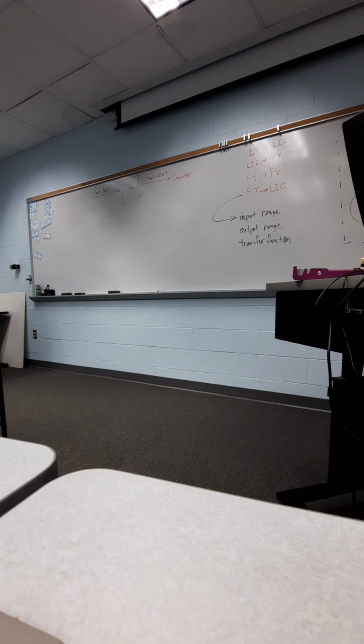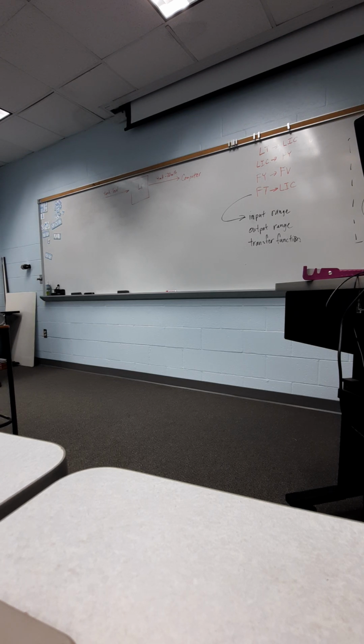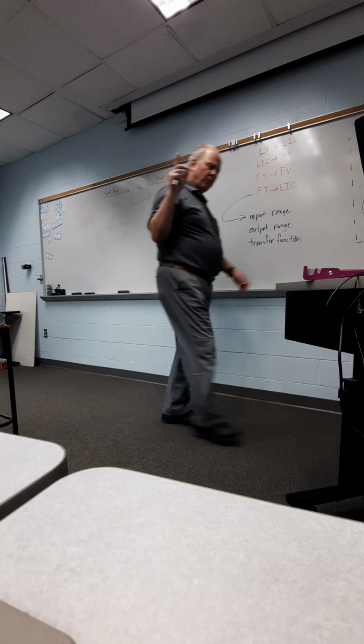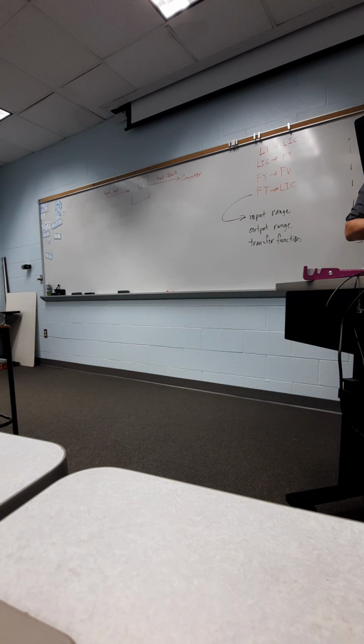So do we have everything we need to set an input range, an output range, and a transfer function here? No. Include the diagram? We kind of do, and it's a qualified yes. Assuming we want to go to 10 inches, from 0 inches, then yes, we would. Now, if we said we don't ever want to go beyond 5 inches, maybe not. Maybe we want to modify the input range. Most likely we don't want to do 20 inches if the tank's only 10 inches high, because that'd be overflow. You never hit it. So there is a limit to the input range that's going to be the top of the tank.